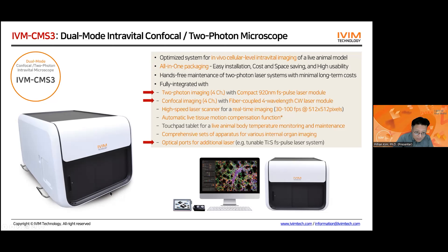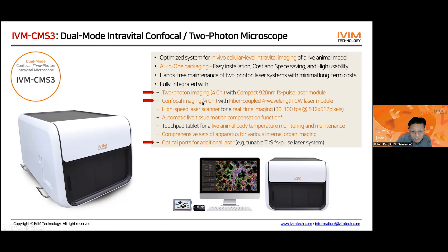This microscope is equipped with a compact 920-nanometer femtosecond pulsed laser for two-photon imaging with four different colors. We can also connect four wavelength CW lasers for confocal imaging, also simultaneously with four colors. There are additional optical ports on the back side of the microscope box for additional laser connections, like a conventional tunable titanium-sapphire femtosecond pulsed laser system for two-photon imaging.